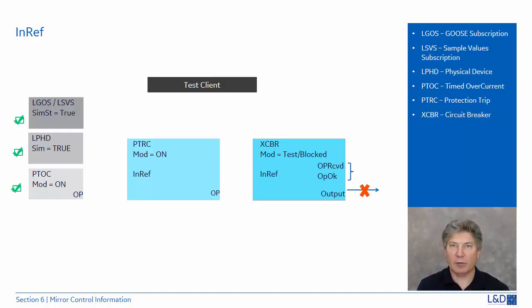We have the phase time overcurrent logical node enabled for operation. The protection trip logical node is enabled for operation. The XCBR circuit breaker logical node is set to test block to prevent the output from operating.